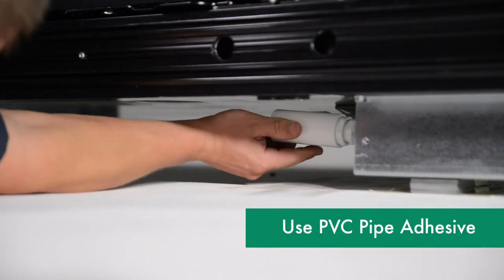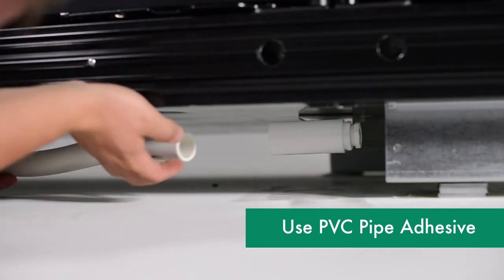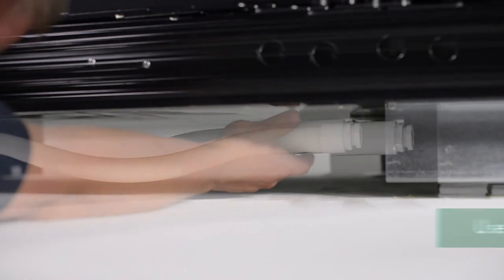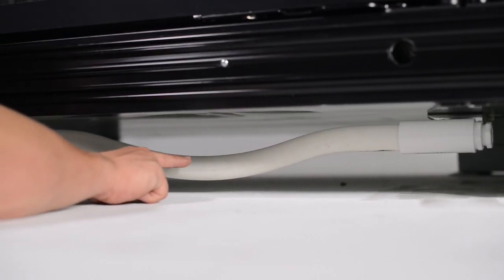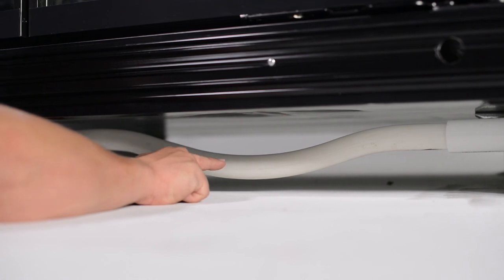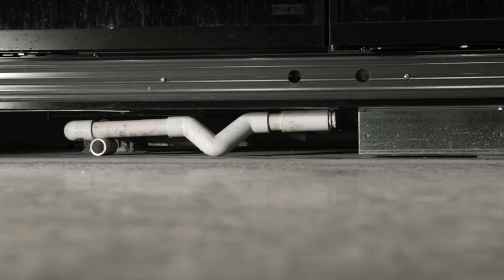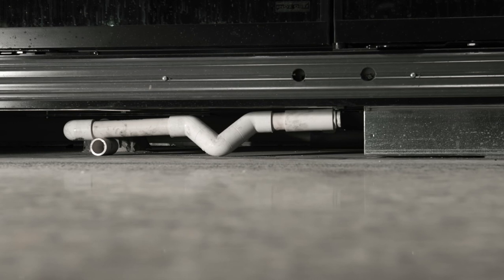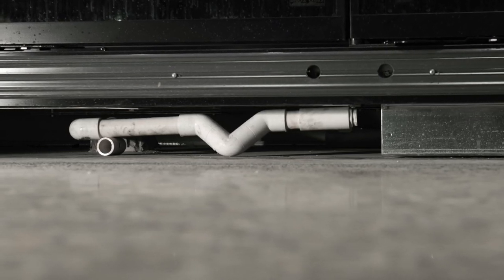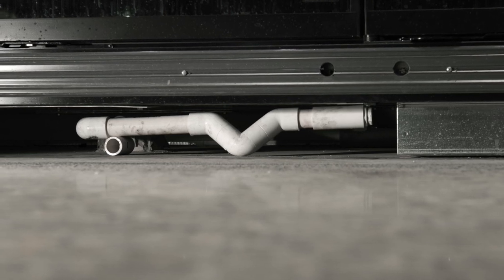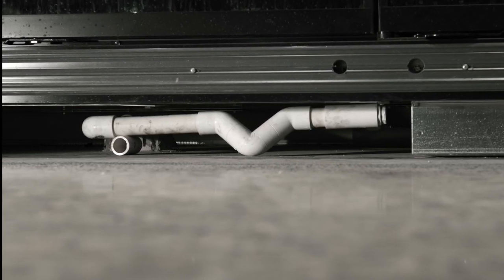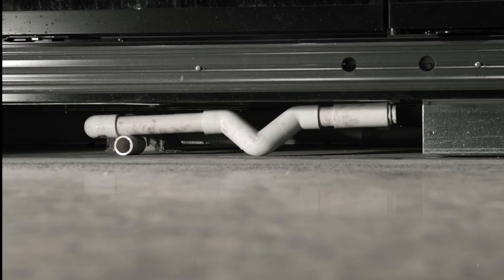Next, install the T on the drain pipe in the direction of your floor drain, then install the supplied running trap ensuring that the trap is level. Each case must have its own drain and be individually trapped. After the running trap, run the drain at a downward slope to the hub drain. Notice, as shown in this photo, an installer may have to field install a drain made up of two 45-degree and one 90-degree PVC elbow. This particular variation was made because the supplied running trap was too long for the final floor drain location and would have overshot the hub drain.